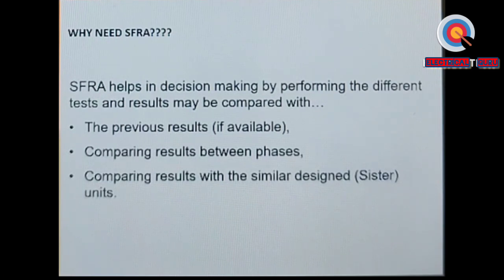Comparing results between phases. In that particular case we deliberately take a reference signature and then compare, but sometimes you have very old transformers and you don't have a reference signature available. So then what you do is compare results between the phases. In the same transformer, if you suspect the R phase has developed some problem, then you compare SFRA of R phase with Y and B and see if there is any disturbance on that phase.